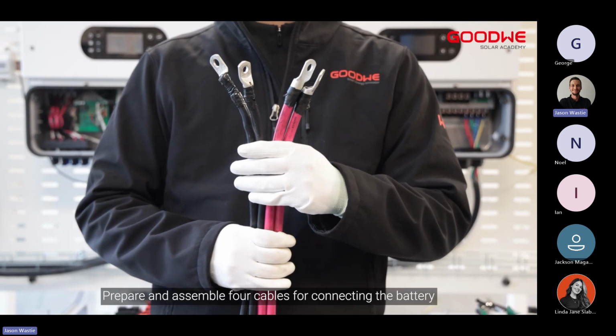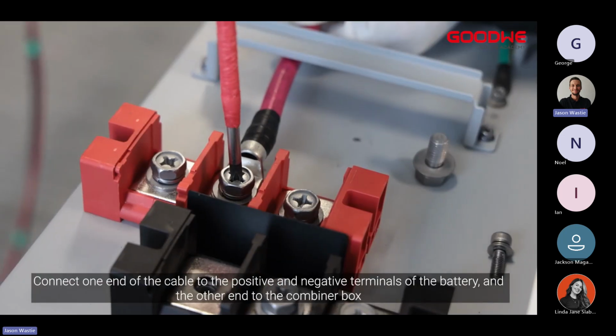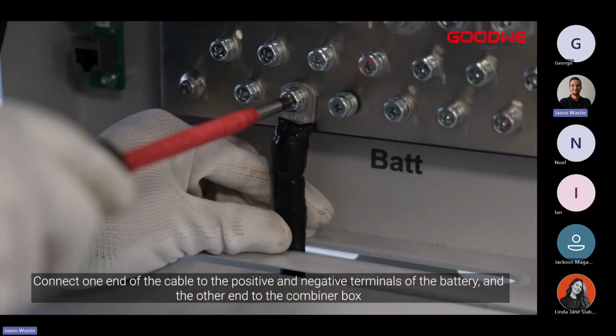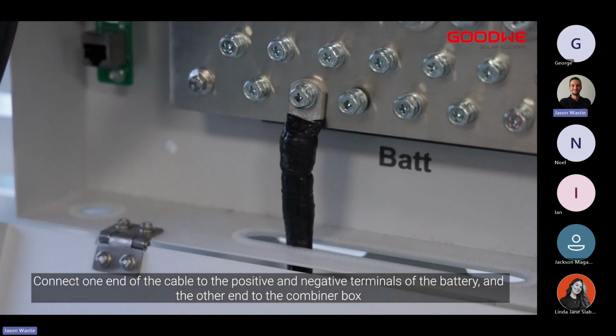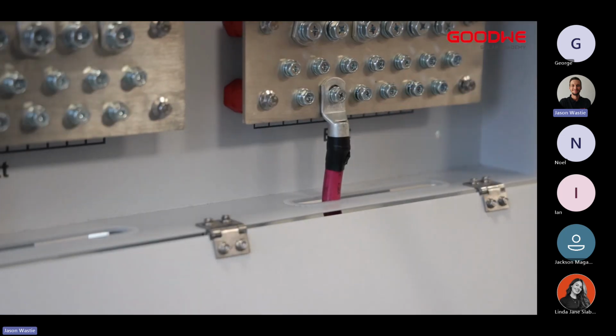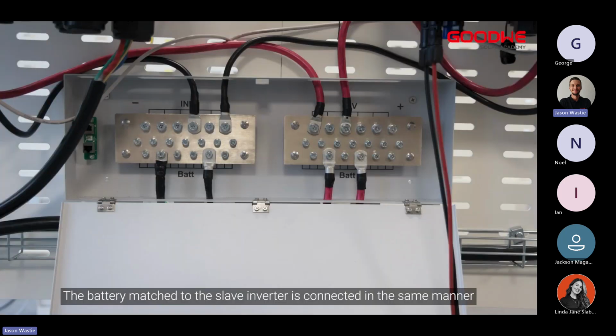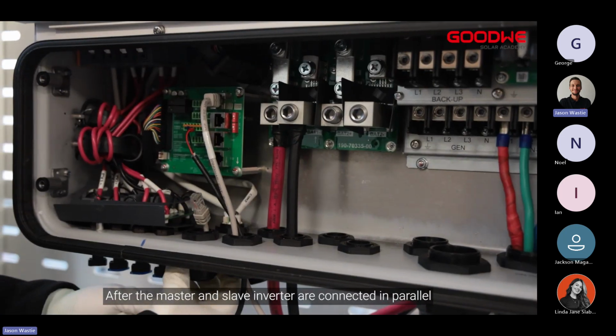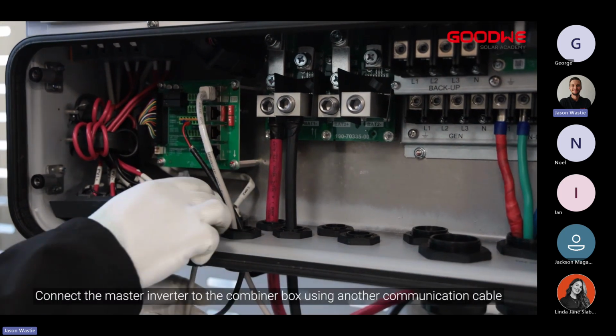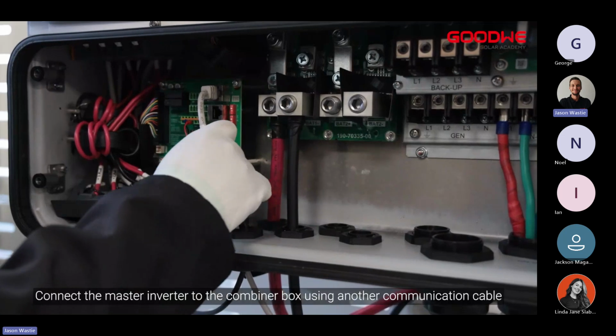Prepare and assemble 4 cables for connecting the battery. Connect one end of the cable to the positive and negative terminals of the battery, and the other end to the combiner box. The battery match to the slave inverter is connected in the same manner. After the master and slave inverter are connected in parallel, connect the master inverter to the combiner box using another communication cable.